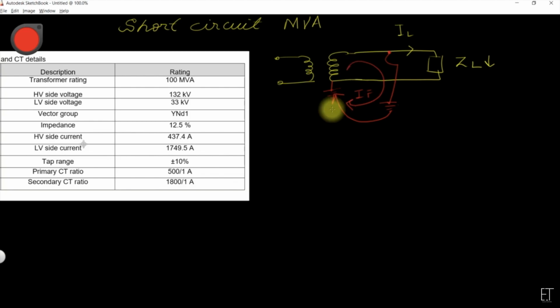In this path, the current will be limited by the impedance. The IF will be equal to the transformer low voltage side (LV) voltage divided by the impedance of the transformer plus the impedance of the line and the earth resistance. So this is all in case of phase to ground.